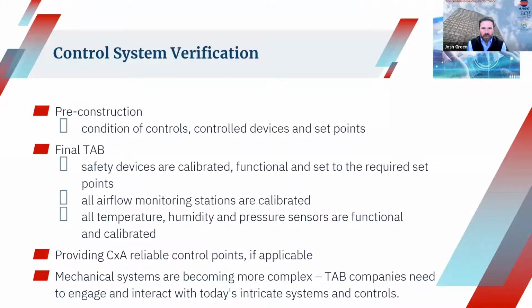One challenge that retrofit projects often face is the field verification and calibration of control devices. If we get out and do some pre-construction, pre-demo testing, we can use that time to document control set points. We've found this is especially important in hospitals and critical spaces. Documenting static pressure set points, outside air set points, and so on prior to demolition and replacement can save time during the final balance and the reprogramming to those pre-demo set points.